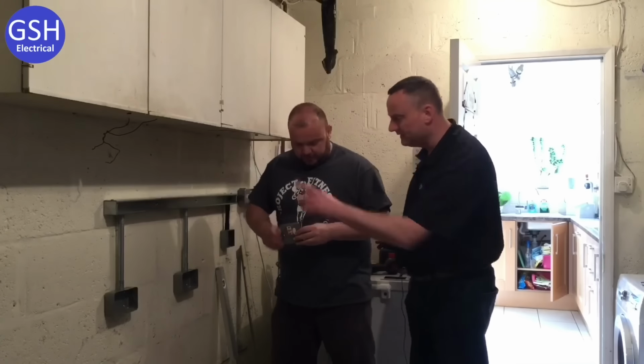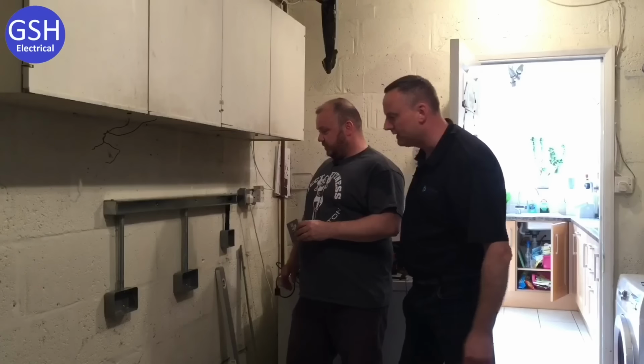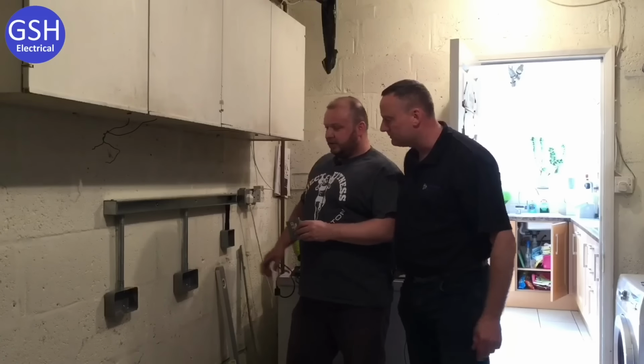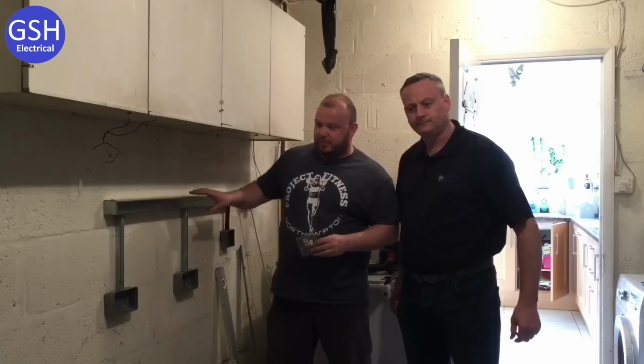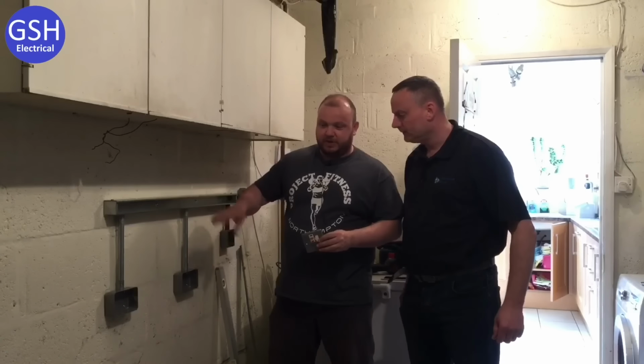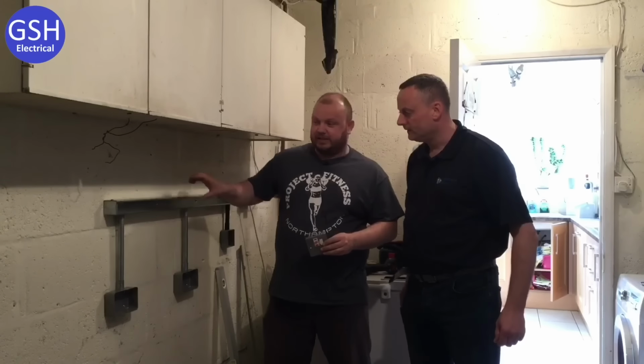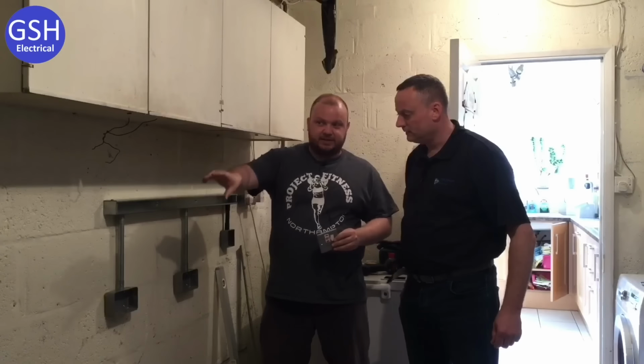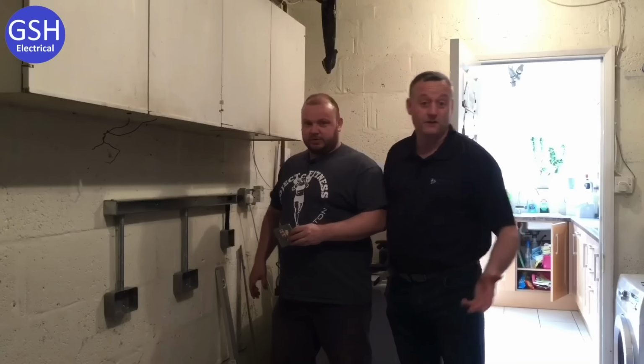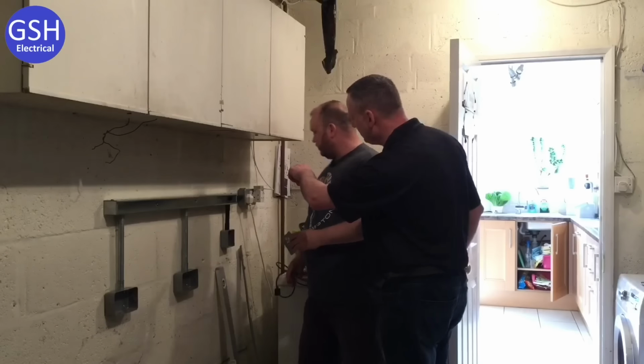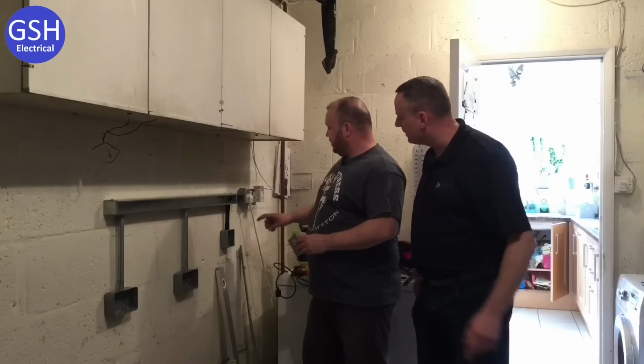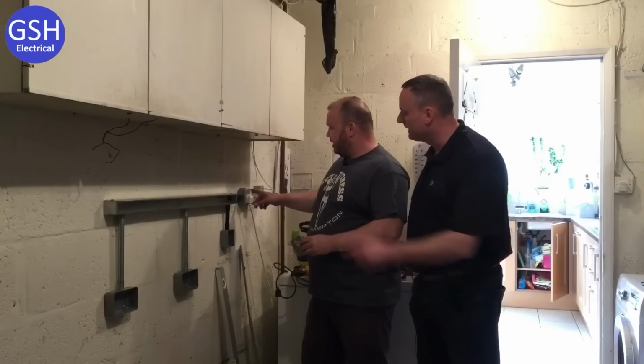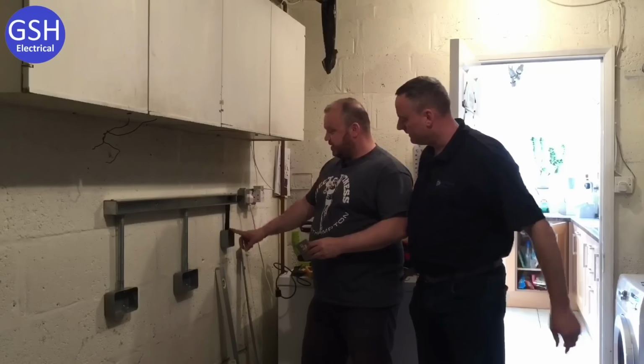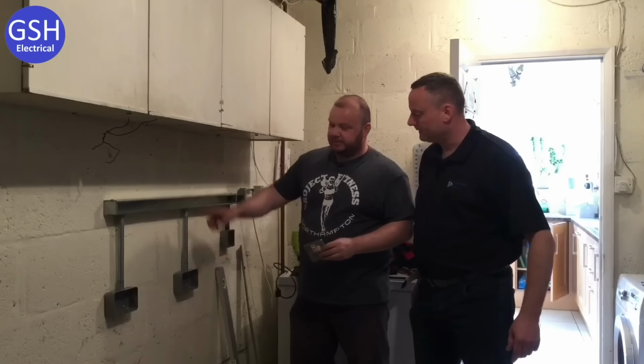Oh, right, okay, brilliant. And it seems a little odd that we've gone for metal trunking, metal conduit in this installation. Can you explain why the customer's asked for that? So basically, we're going to be building a workshop, and this is basically the start of it. This has been put in place so that it can be extended further down the wall. Okay, that's fair enough. So it's a fair point. So we've come off an existing socket outlet. Did you prove that was on the ring final circuit? So this is on the ring final circuit. Brilliant. Okay, and we're going to spur off that into the RCD. Yep. Back out and then back into those.